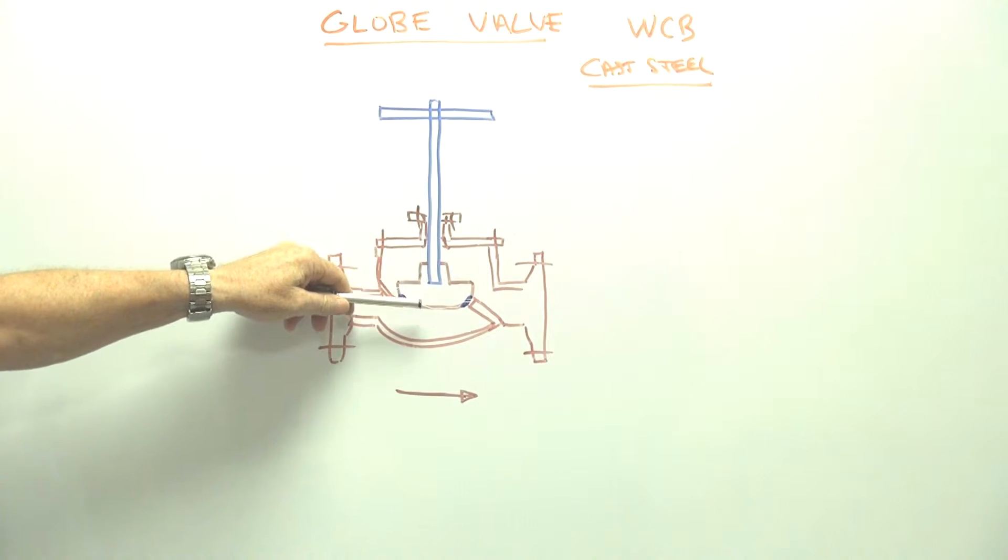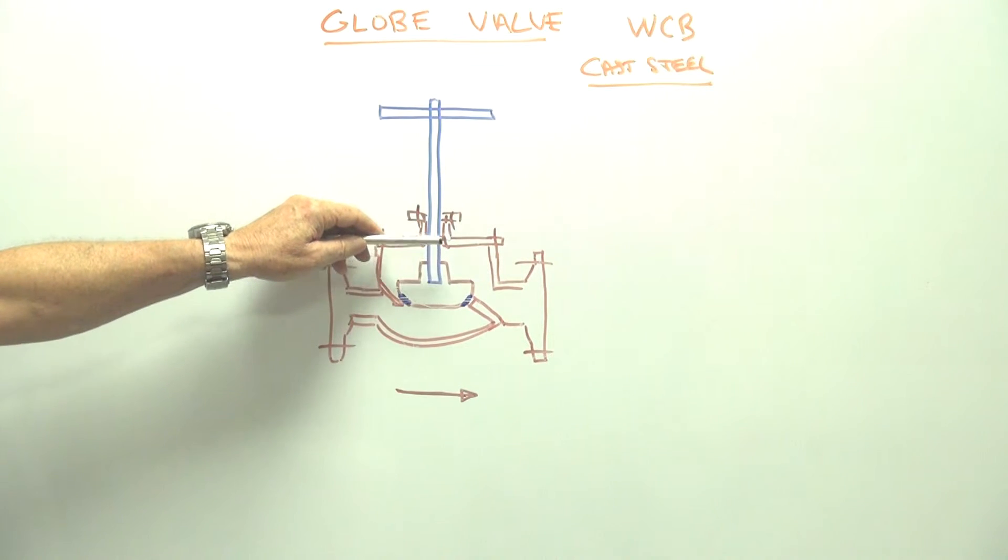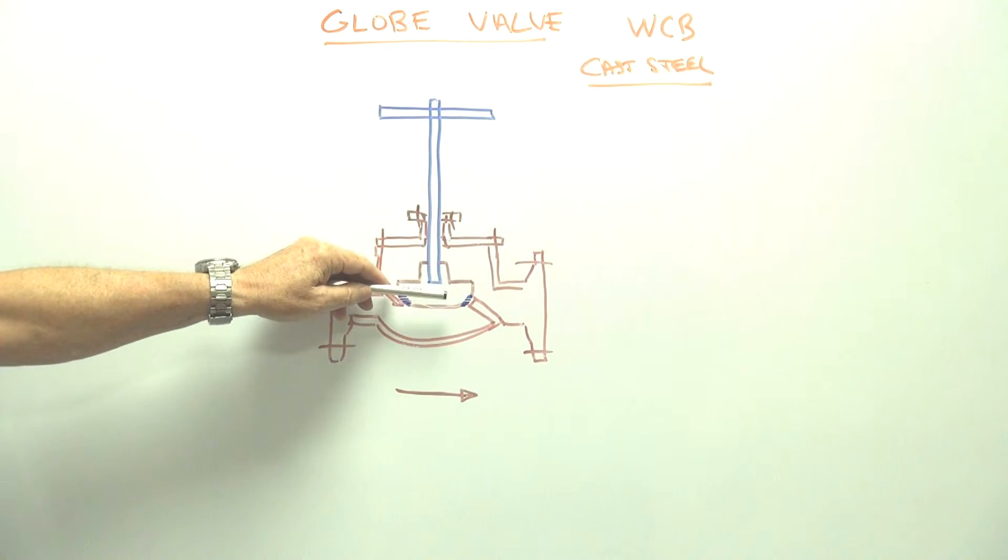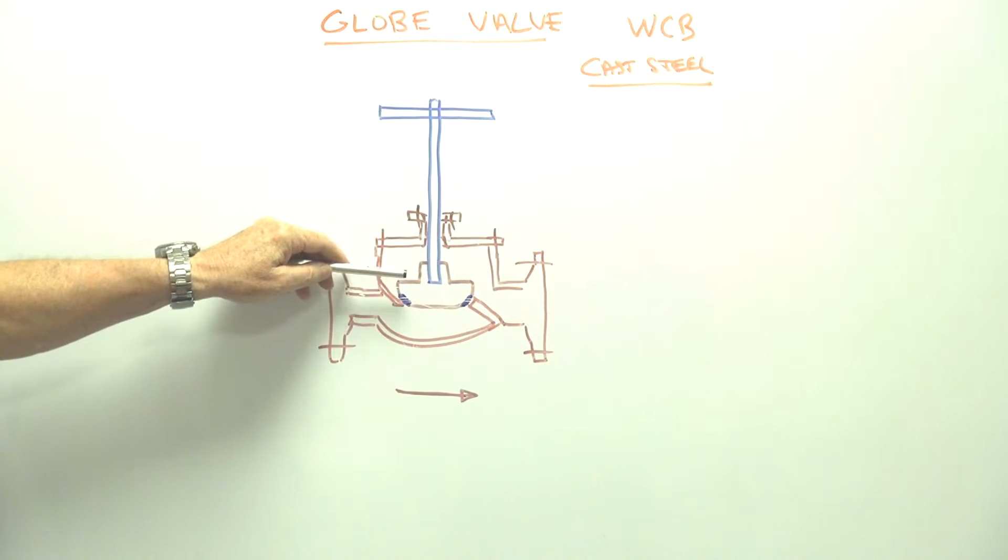As it comes up and down because of the globe shape it gives you a proportion of control. Now this is good over other gate and ball valves because you are getting this flow control effect due to the fact that as it drops into the valve cavity it's giving a proportional opening up of the flow.